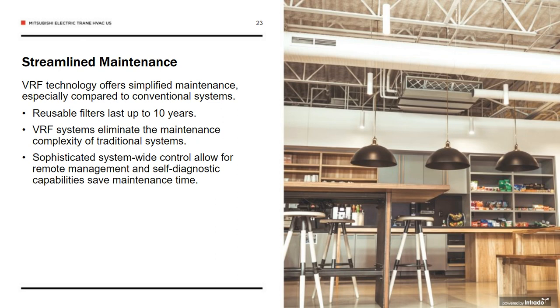Right? They could view the errors that tell you exactly what the issue is, and they were also able, via the onboard maintenance tool that we have, to see temperatures and pressures without having to get out on the site and up on the roof first. It was like looking at the equipment from their computer. So with less time for maintenance calls, they were able to focus on the real issues that they had within their site. So it became a problem issue. VRF came in and was able to deliver a great solution for reducing long-term operational costs.